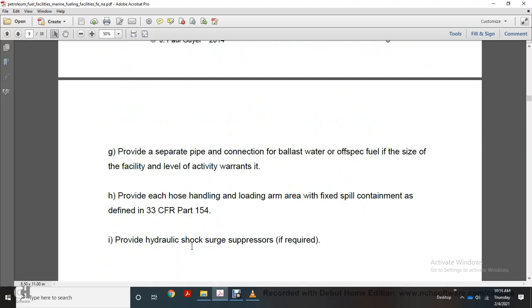Provide a separate pipe connection for ballast water and off-spec fuel inside the facility when the level of activity warrants it. Provide each hose and loading arm with a fixed spill containment as defined in Title 33 CFR Part 154. Provide a hydraulic shock surge suppressor if required.